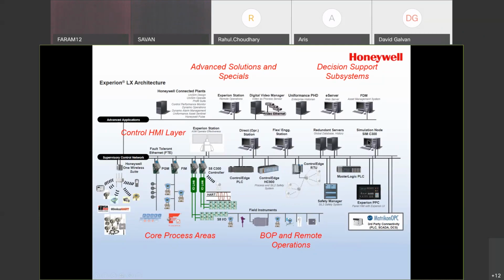Okay. Experion, the ControlEdge PLC, the ControlEdge RTU are fully capable of simulation. So I can simulate the C300, I can simulate the ControlEdge PLC, I can simulate the UOC, the Unit Operations Controller, I can simulate the RTU. So again, you can do all of your engineering, your programming, your testing way ahead of time, way before you have the hardware in your hands. And then once you prove that, you can dump all that logic into the physical hardware. But more importantly, as you go forward, with the life of the product, you can actually use simulation for testing.